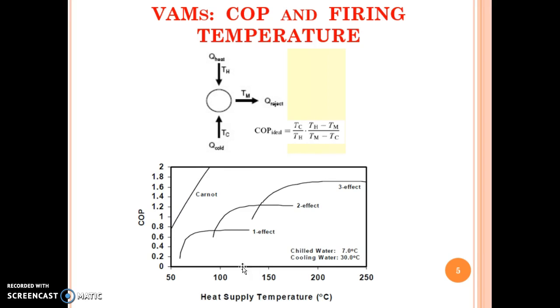So as the temperature increases, the efficiency increases nearly linearly. But the real machines cannot provide such high efficiencies. As it can be seen, if it is a single effect vapor absorption machine, this is the efficiency you get as the temperature rises, but at higher temperatures the efficiency becomes flat.